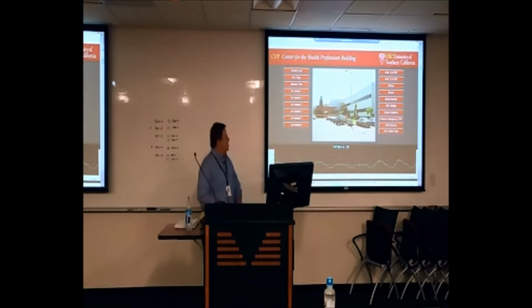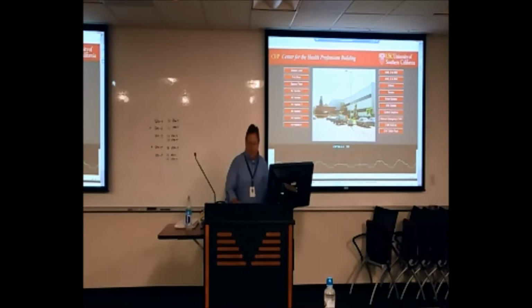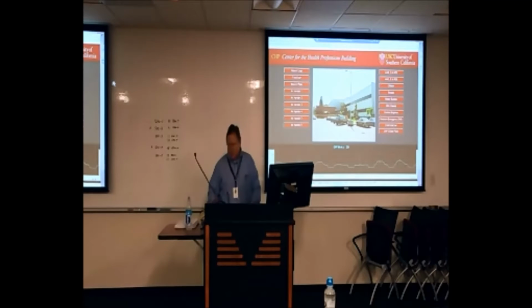But for now, we're going to take a peek at the graphics and go over the sequence of operation for the cooling tower. First off, as an overview, this was a cooling tower replacement. There was an existing cooling tower for the CHP plant. So there's a CHP plant controller, then there's a CHP cooling tower controller, and the cooling tower was relocated from the east side of the building over to the west side of the building. And so with that came a brand new controller and a modified sequence of operation.